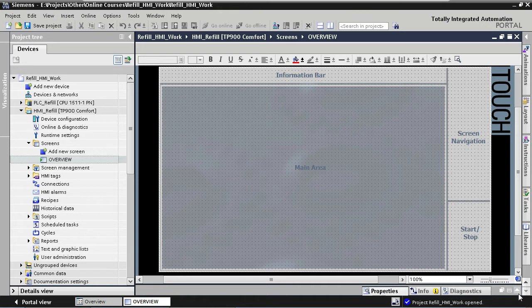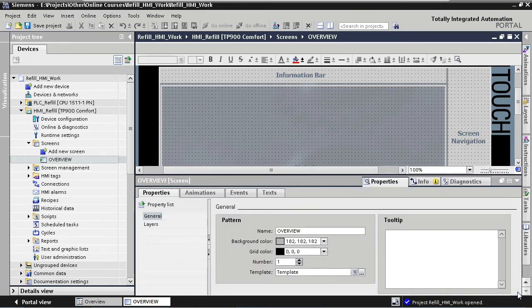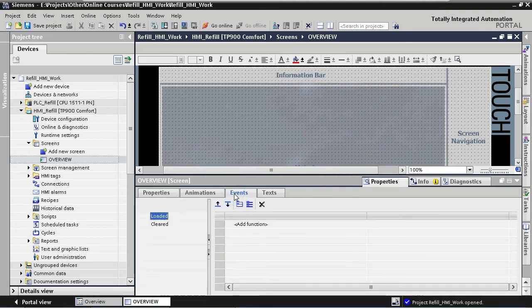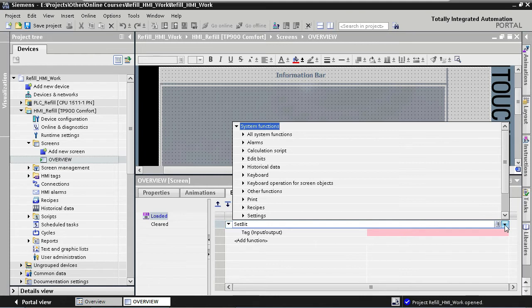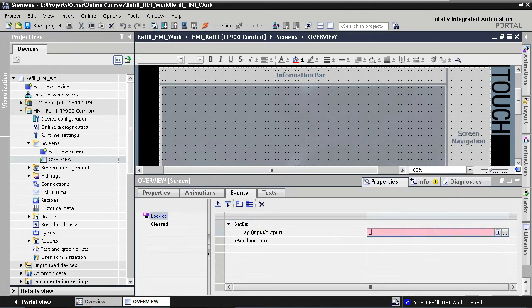We implement this feature as follows. On the overview screen we go to Events instead of Properties. Here you can add a function for when the screen is loaded or cleared. Under Loaded we add the Set Bit function, which will set our boolean tag to the value one. We press Add Function and start typing 'Set Bit' — TIA uses autocomplete, so it's very easy to find and assign functions. Alternatively you can use the downward arrow on the right to get a list of all possible functions. We assign our tag and done — when the screen is loaded, this event will set the boolean tag to one.